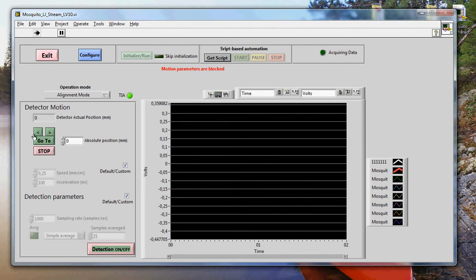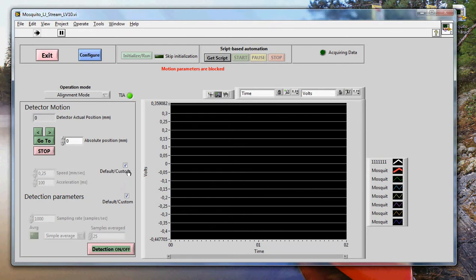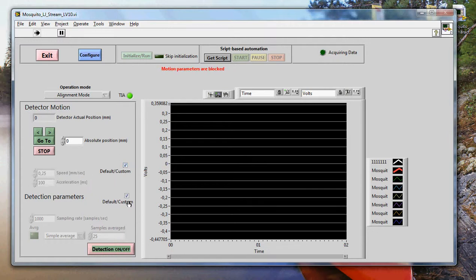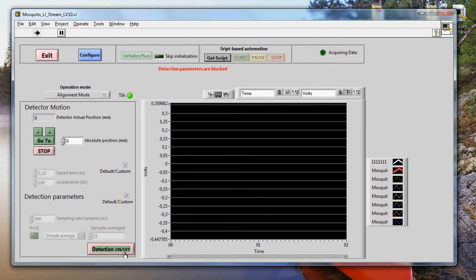These buttons here are related to the piezo. This allows you to move the piezo system. It is only for one axis of motion. Here you can change the speed and the acceleration of the piezo. And this is where you control the detection parameters. How many samples per second it requires. And if you want to do some averaging on the acquisition or not. So let's see how it works.